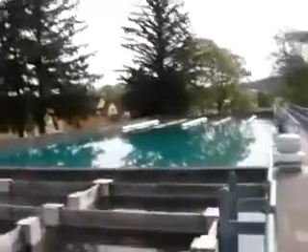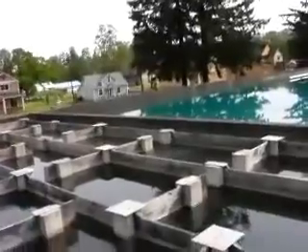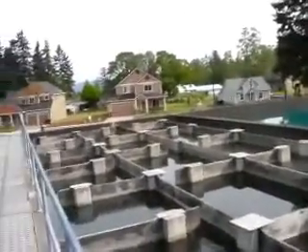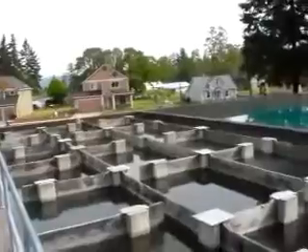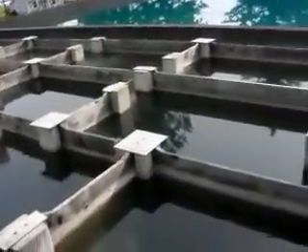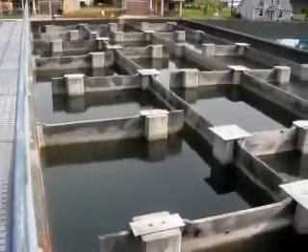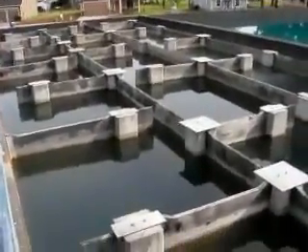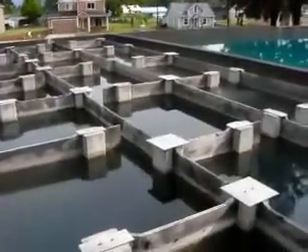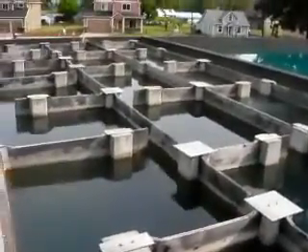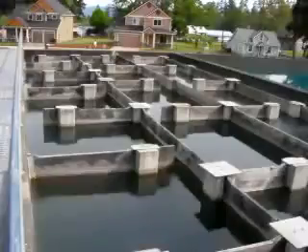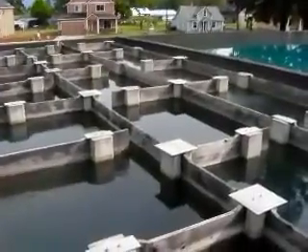And so as you come through, the water flows out here, this is our serpentine flocculators. The serpentine, pretty obvious how it follows the name. The key is you see how you have some turbulence in the water here, but at each stage you want to slow it down. Can you see the difference between each stage? That's the key. And then out there you want to be barely moving because you don't want to shear the floc.